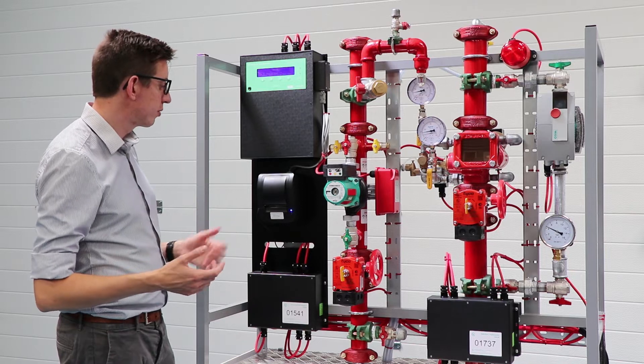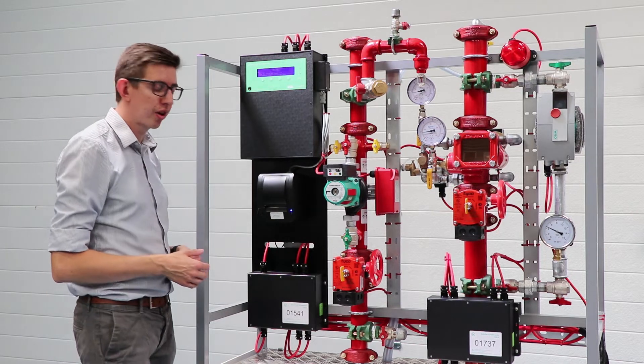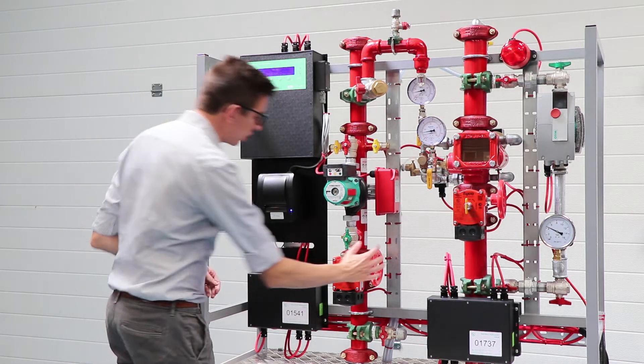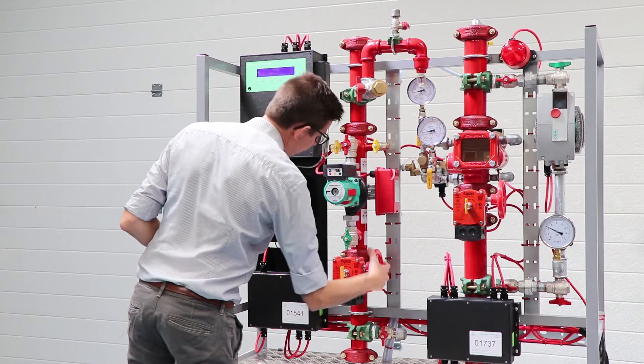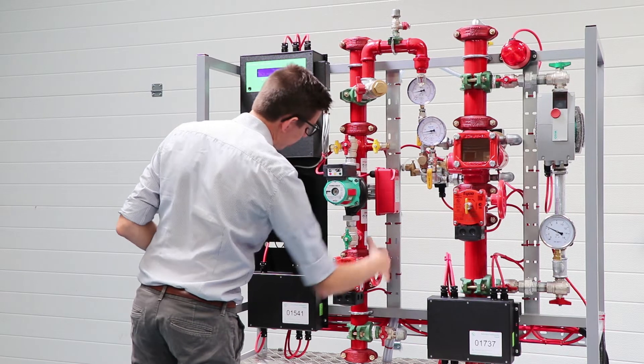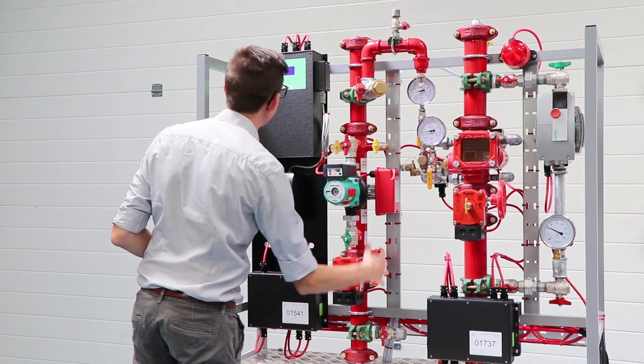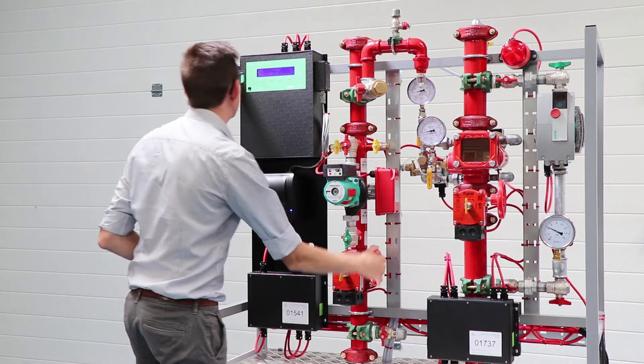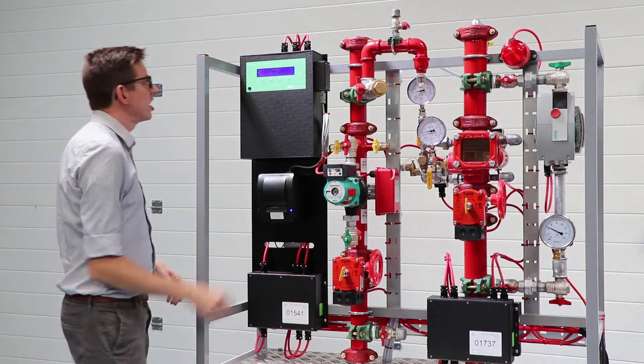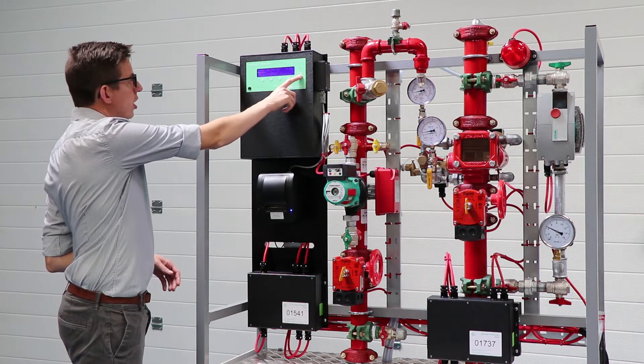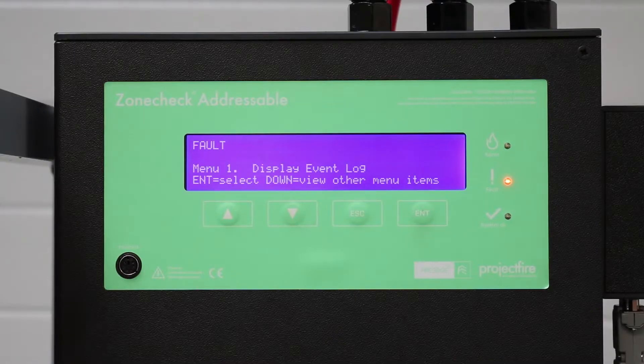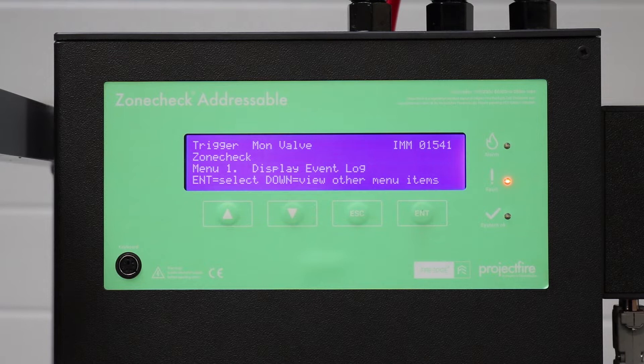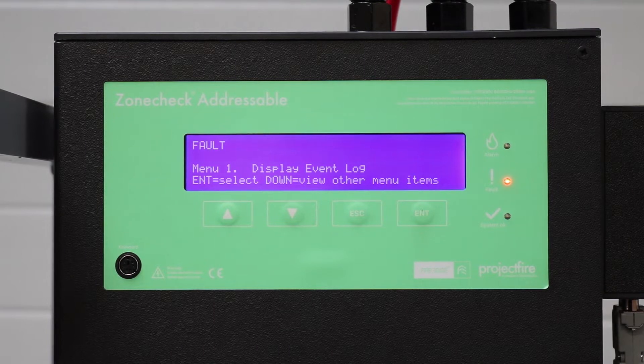If something was to change — say someone goes and closes one of those zone valves — I can show you here. I'm going to start closing this zone valve. And we can see here our controller has gone into fault mode. It's telling me there's a fault, telling me what's happened, and telling me where in the building that it is.